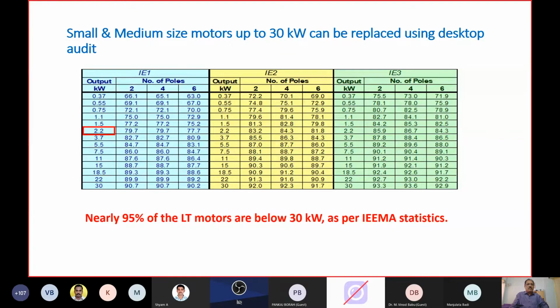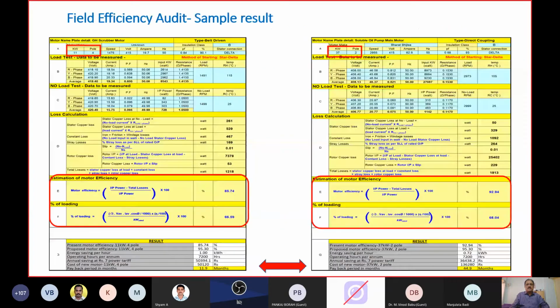I have a slide here where we talk about the increment between IE1 and IE3. A case is a 2.2 kilowatt 4-pole motor whose original efficiency was 79.7, which becomes 86.7 in the case of IE3. Using this chart, as I already told you, around 97% of the total motor population is below 30 kilowatt as per the IEEMA statistics. We can undertake a desktop audit, with which an Excel sheet calculation will give the management the encouragement to invest and replace motors up to 30 kilowatt without doing any load mapping or profile mapping. So that is the choice available to industries.